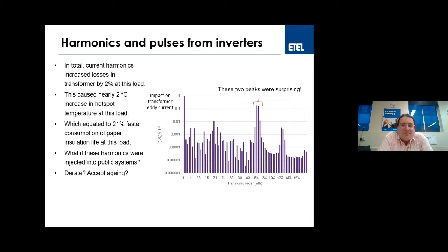Now, this slide here, one which we took from Australia. This is a transformer attached to a solar farm. We were very surprised when we measured these harmonics, that we found these two peaks around the 60th harmonic order. So these were two peaks due to current harmonics around the 3 kilohertz range. And we were very surprised when we saw them, because it looks like with inverters now coming in on the grid, they might actually start to heat up the transformer a bit more.